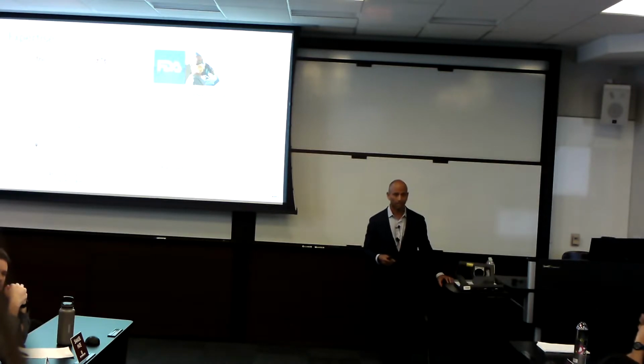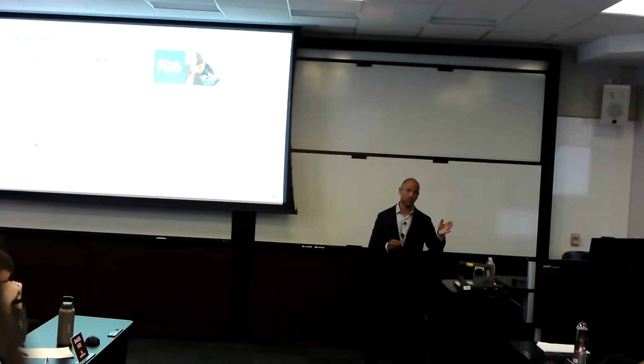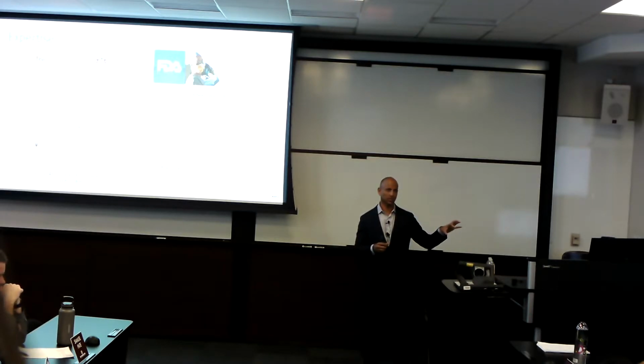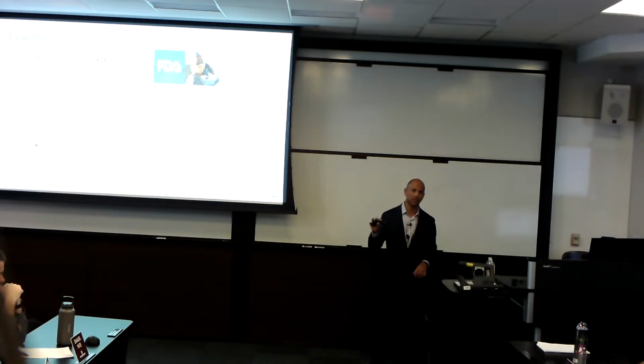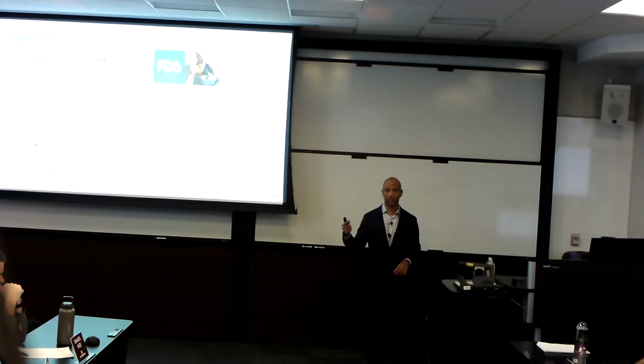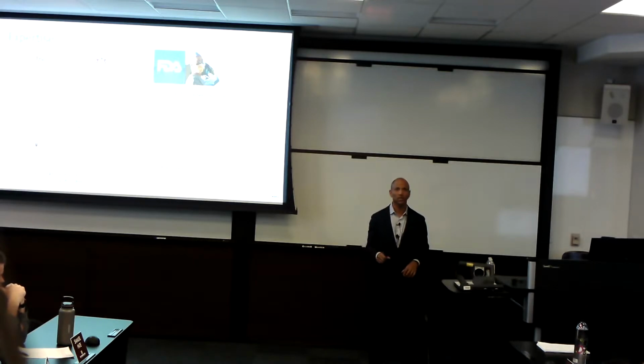I know there's a difference between FDA approval and FDA cleared. Can you explain that difference? Clearance is when you're filing a 510(k). There are 2 main regulatory pathways for devices. The 510(k), where you're proving you're substantially equivalent to something on the market, is generally for lower risk devices. There's also the PMA, which is a premarket approval application, where a lot more testing and a lot more data, usually clinical studies, are required, and those take a lot longer. Those are multi-year processes with FDA. The 510(k) is on average 6 to 9 months to get through FDA, but again, that's 6 to 9 months after you've done all the development testing and everything else, which is a 2 to 2.5 year process.